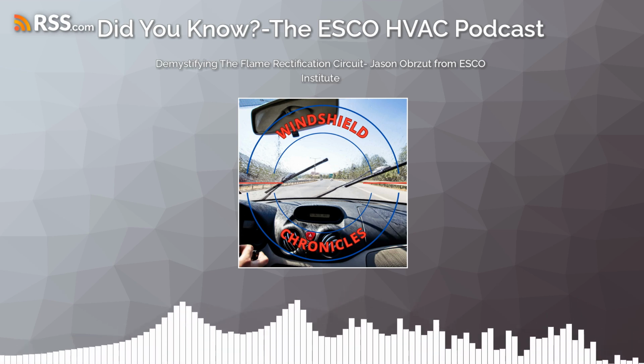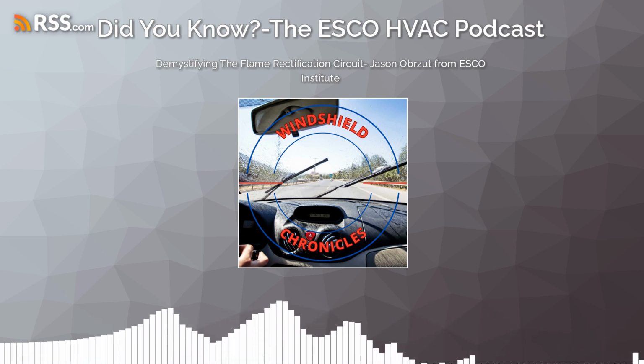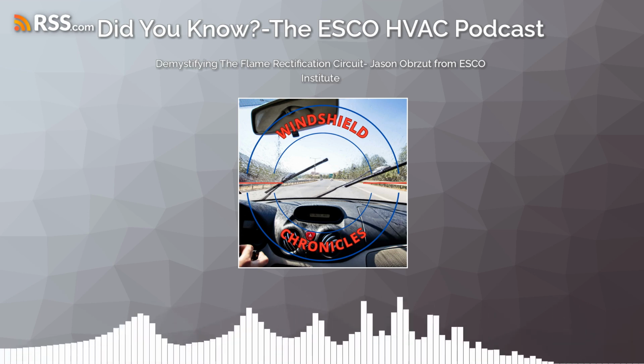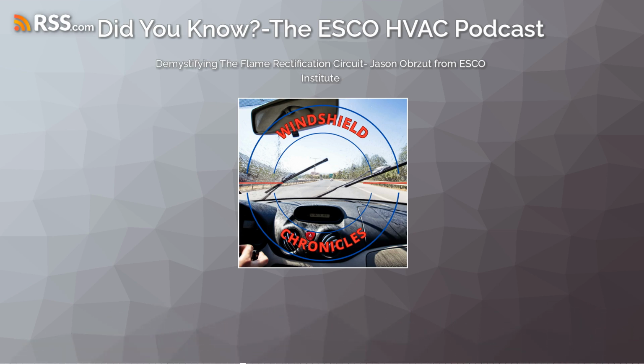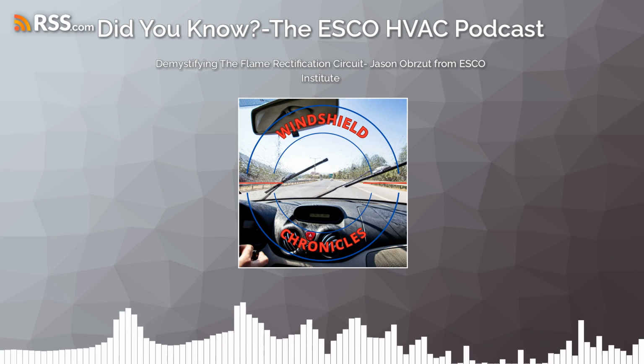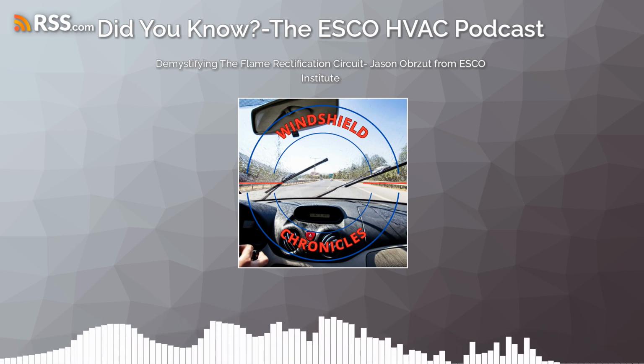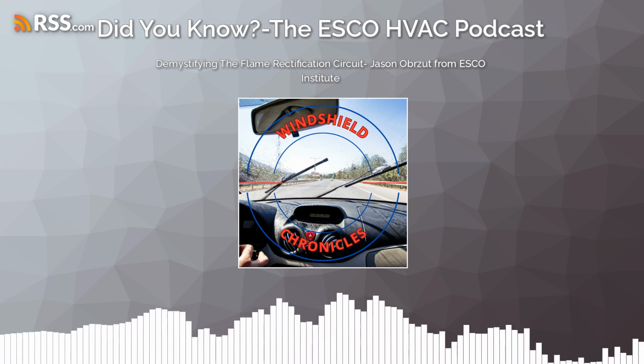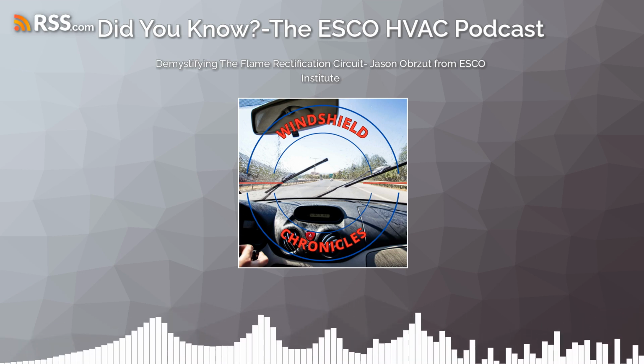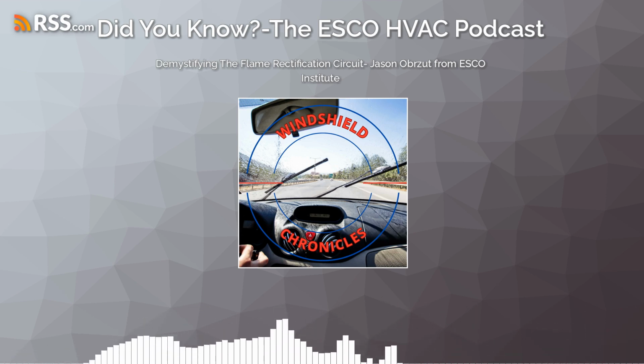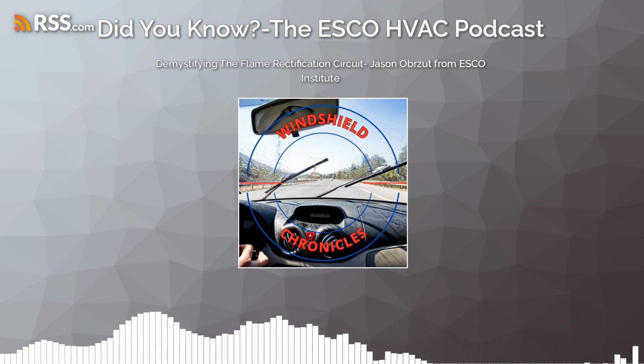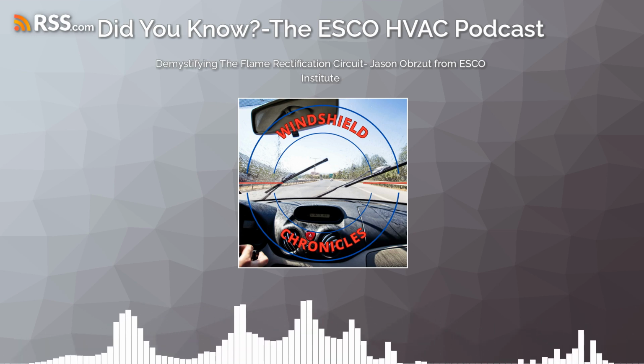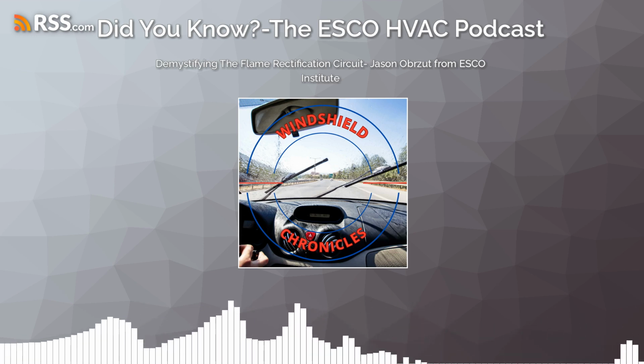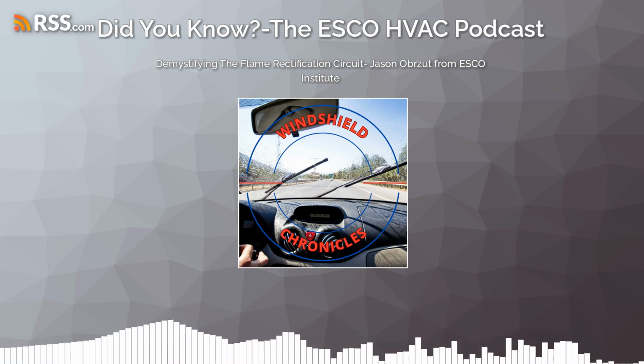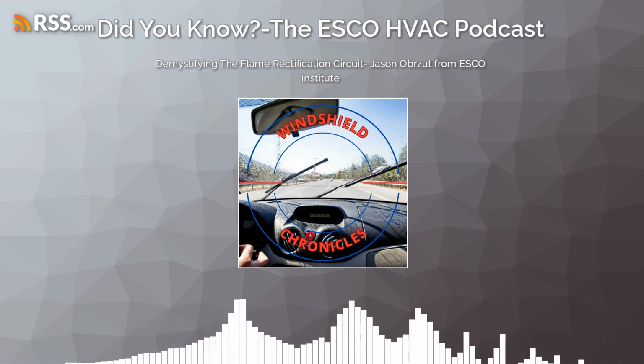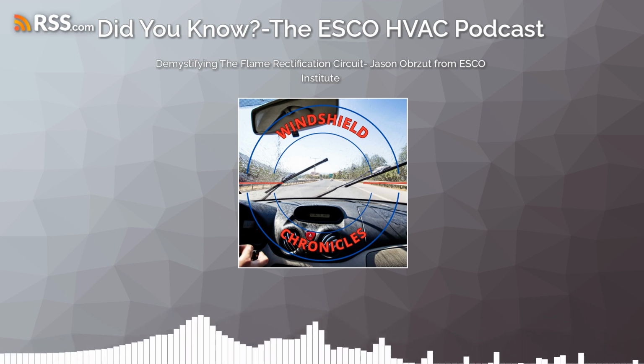And we're putting a load on that flame, which is why we are reading in amps. So we're putting a very, very small amount of voltage through it, and we're putting a very, very small load on that flame. So we're reading it in microamps, and we're reading it in a DC voltage. Okay. It is basically half of the sine wave, because the flame does have a very high resistance. The circuit board is usually only seeing about half that sine wave, and on your meter, you're only going to see about half that sine wave, which is why it shows up in DC and not AC, right? Exactly. But it is 100% AC voltage. I'll even show you on a wiring diagram. A lot of people have missed this. When you read your wiring diagram, it'll completely make sense.